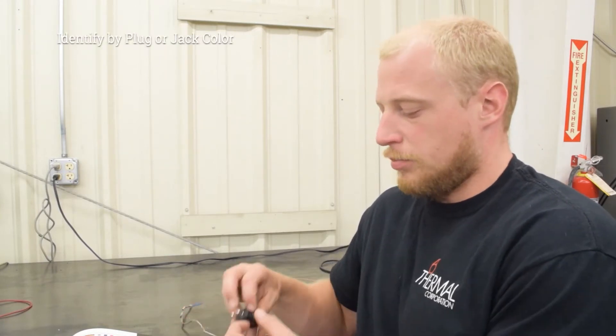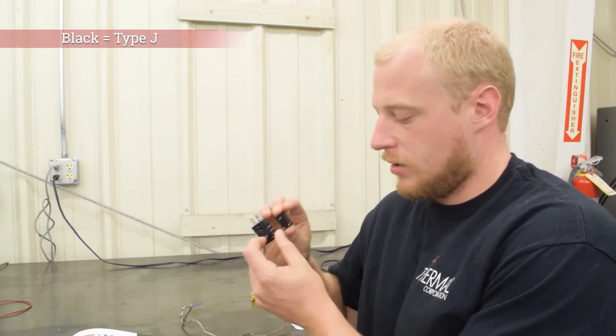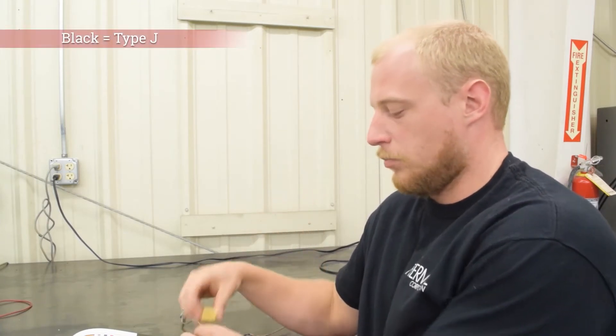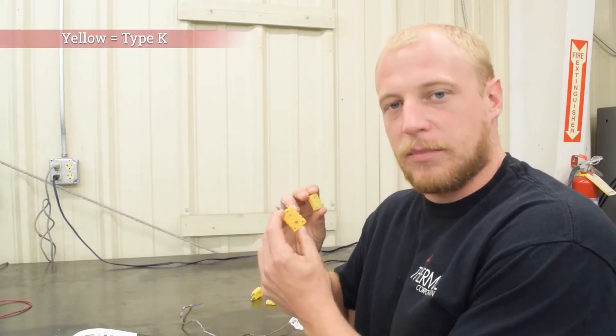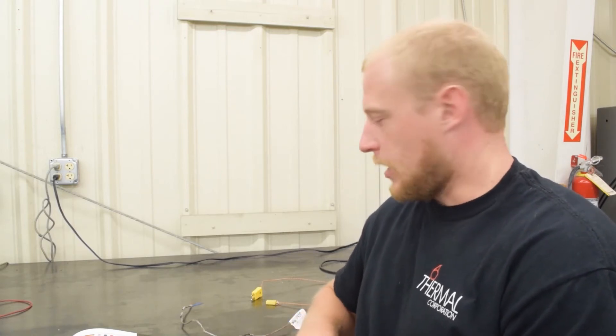So the first indicator is going to be the plug or jack color. Black is going to be a type J thermocouple. You see a yellow plug and jack, that's going to be a type K thermocouple. Blue is going to be a type T thermocouple and white is going to be not a thermocouple but an RTD and we'll discuss those in a later video post as something completely different. So that's your first indicator.